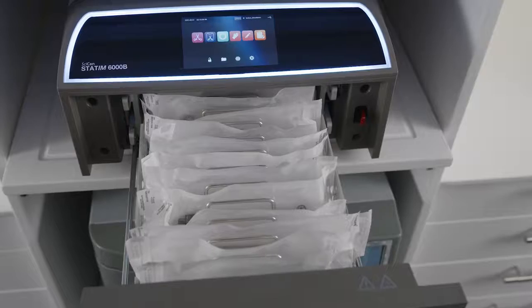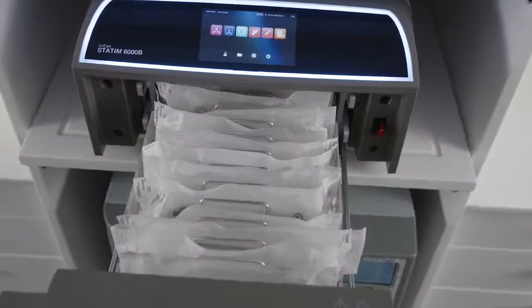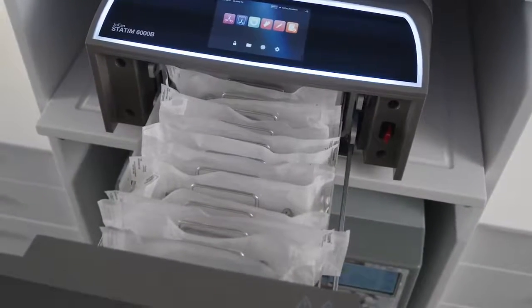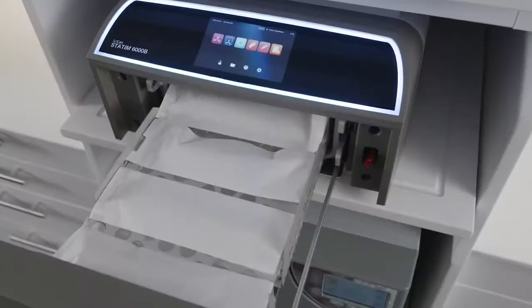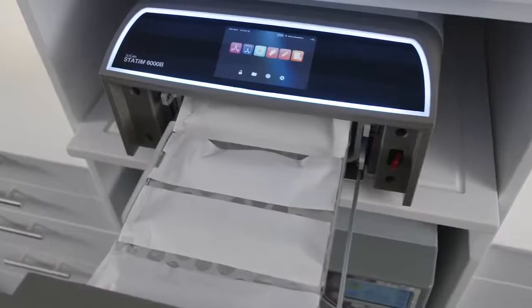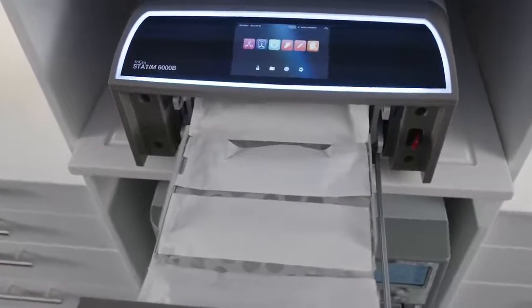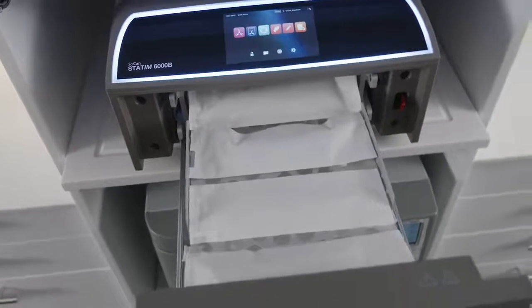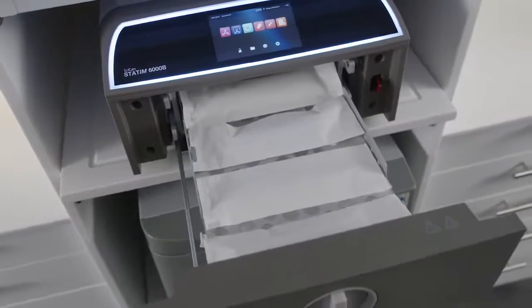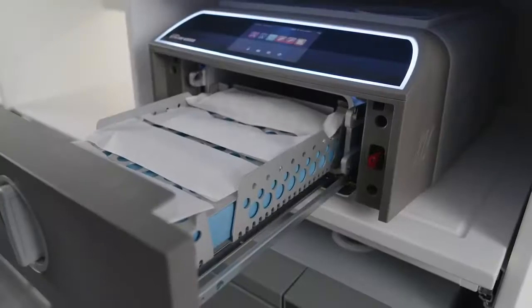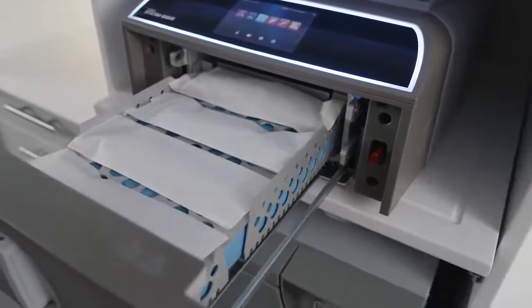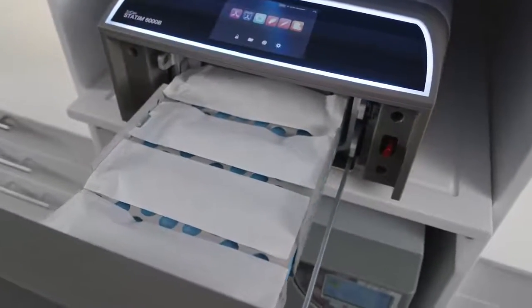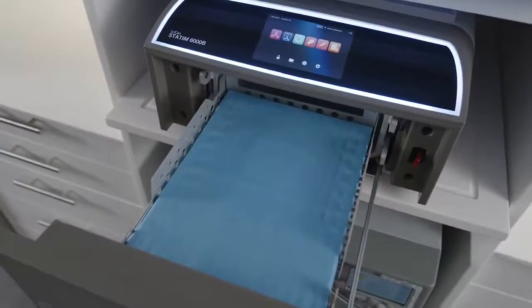The STATIM B also includes a separate pouch rack that enables you to process up to 12 pouches in a load. The STATIM B can also process pouches using the standard trays. In this configuration, you may load 4 pouches on each tray with the paper side up. You may also sterilize a load that contains a mixture of both pouches and cassettes, or just a single cassette.